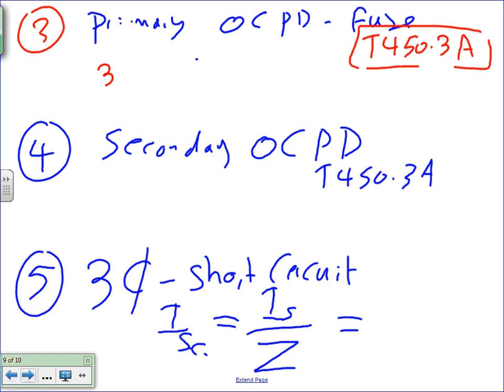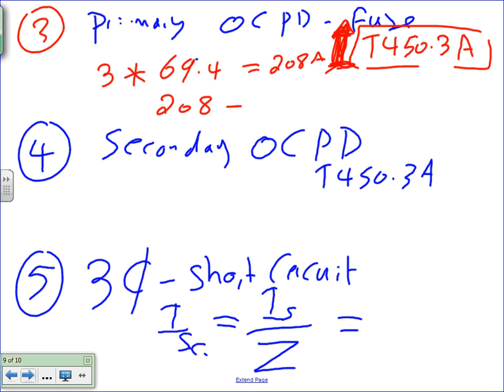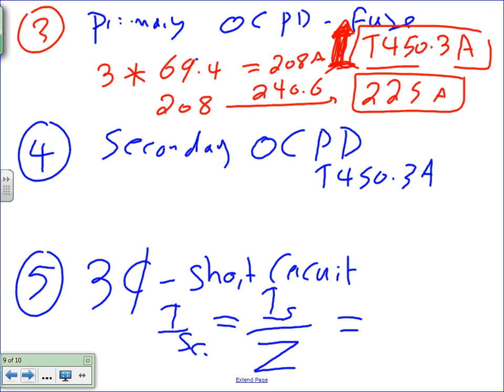The primary says 3 multiplied by 69.4. That will get you a healthy 208 amps. This is from 450.3(A), in the Code book. And if it's not a standard size, you can go up. If you go up, you take the 208 to 240.6, and that gives you 225 amps. 225 amps. Any question about this, guys?